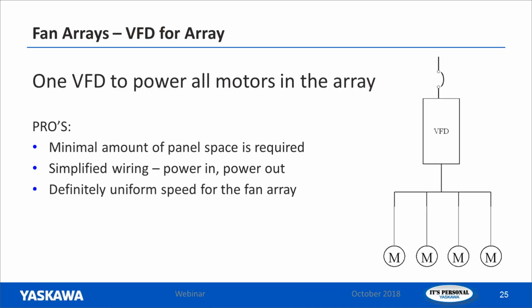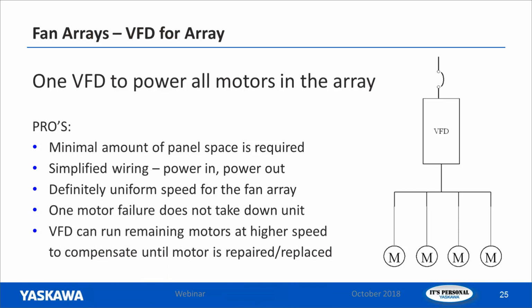Now you're definitely going to have a uniform speed for your fan array because that VFD is going to be putting out the same frequency. So as long as you've got the same motors, they're all the same and not different RPM, same frequency is going to be running them all at exactly the same speed. And now one motor failure is not going to take down your whole array because you could still just run the remaining motors. And the VFD can do just that. It'll run the remaining motors, and it can run them at a higher speed if necessary to meet the demand.